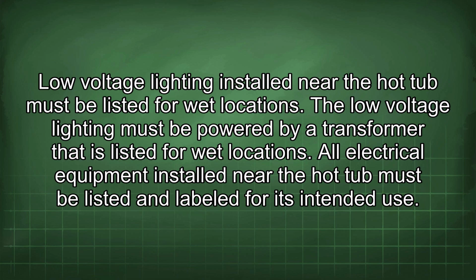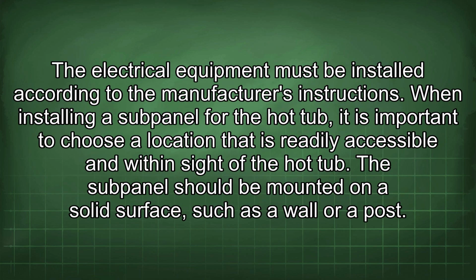The low voltage lighting must be powered by a transformer that is listed for wet locations. All electrical equipment installed near the hot tub must be listed and labeled for its intended use. The electrical equipment must be installed according to the manufacturer's instructions.